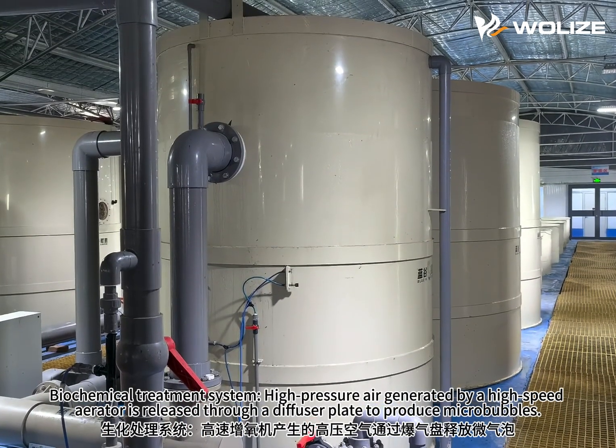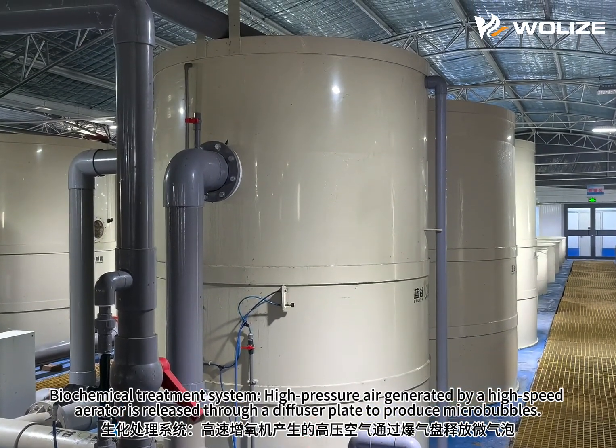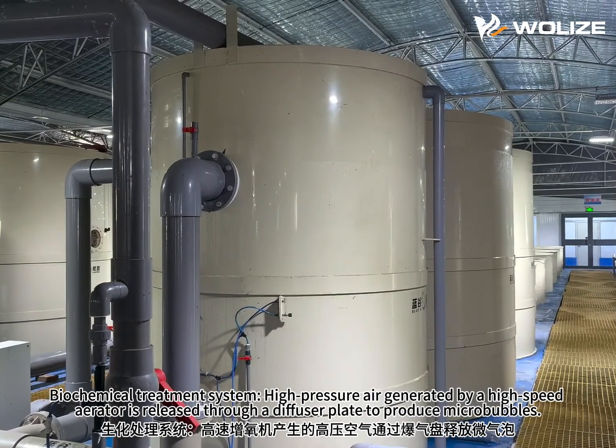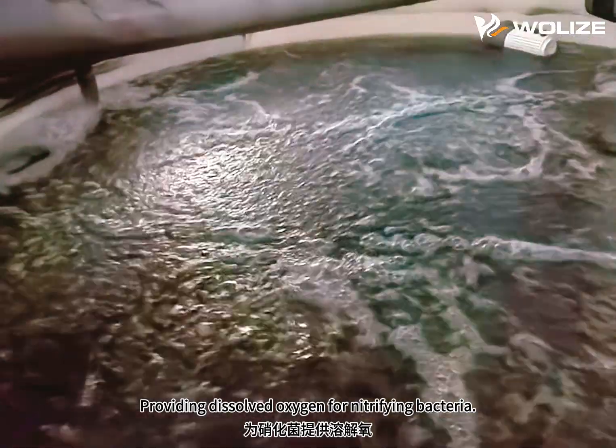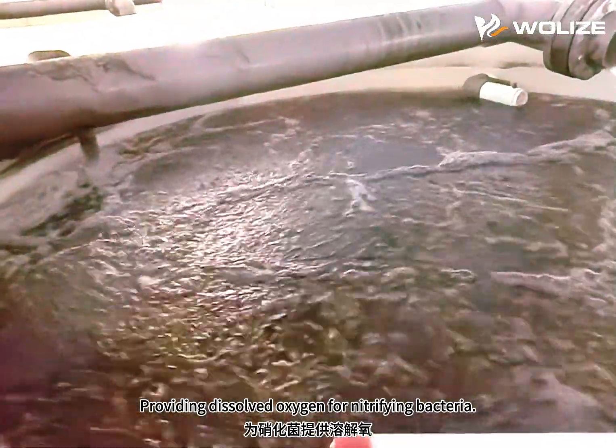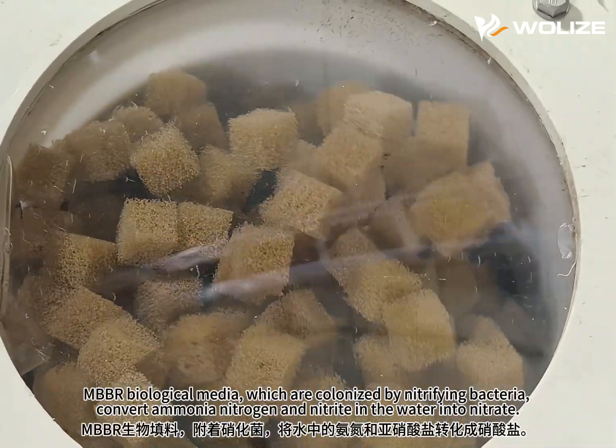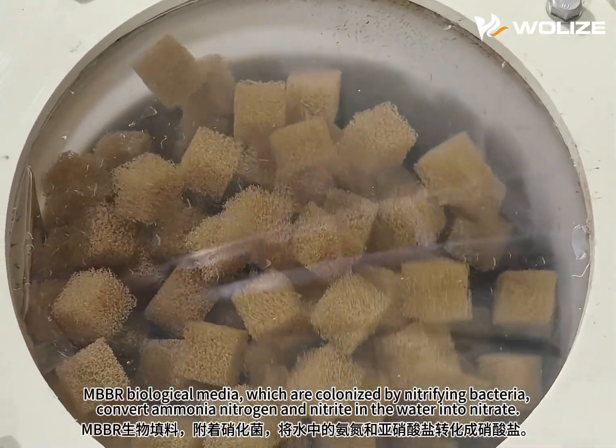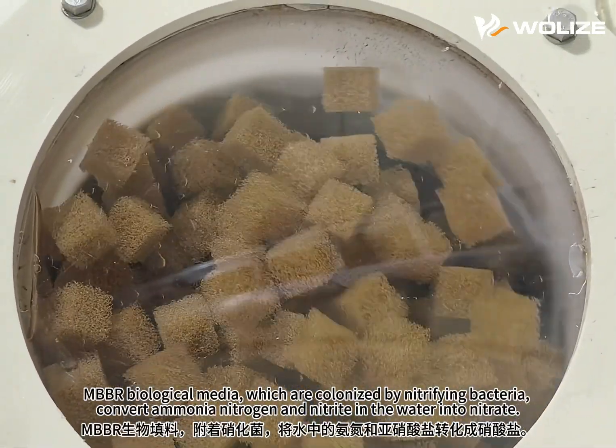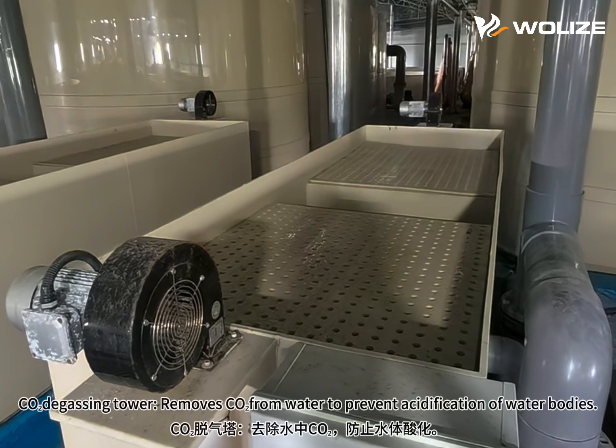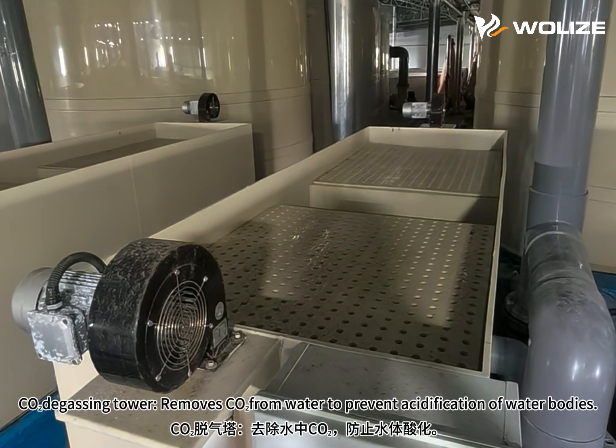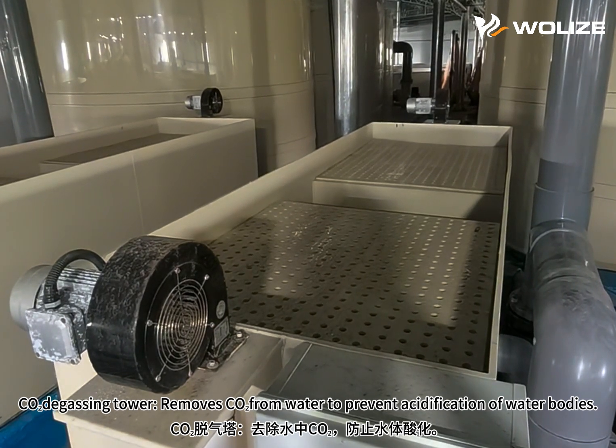Biochemical treatment system: high-pressure air generated by the high-speed aerator is released through a diffuser plate to produce microbubbles, providing dissolved oxygen for nitrifying bacteria. MBBR biological media, which are colonized by nitrifying bacteria, convert ammonia nitrogen and nitrite in the water into nitrate. The carbon dioxide degassing tower removes carbon dioxide from water to prevent acidification of water bodies.